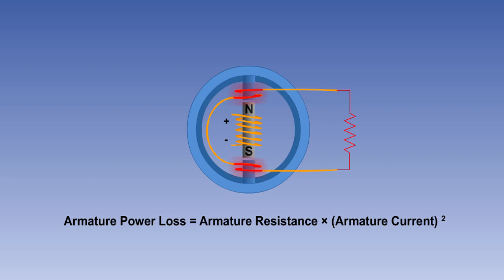This power loss heats up the conductors and can, in extreme cases, destroy the insulation of the windings. For this reason, AC generators are rated in terms of this armature current, as well as by their voltage output.